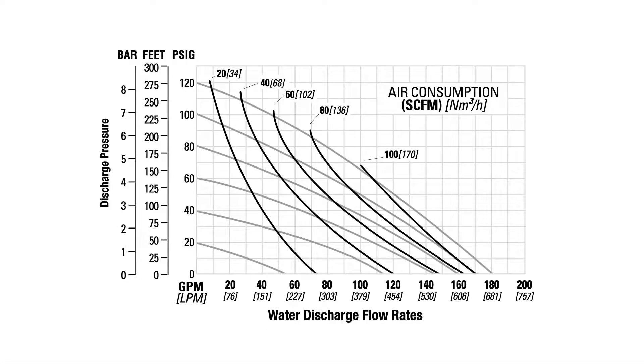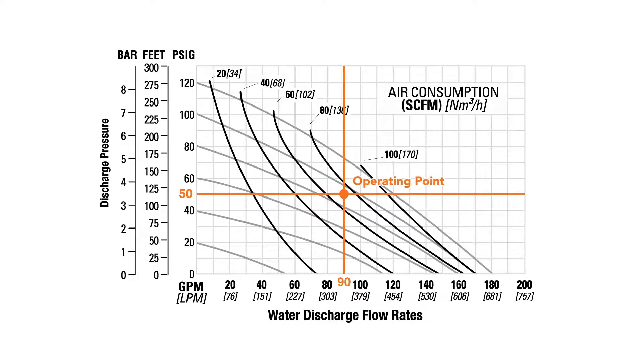The AODD pump performance curve also defines the pump's air consumption, which can be used to help size a compressor for your system and identify opportunities for cost savings. Using the same operating point — pumping 90 gallons per minute at a discharge pressure of 50 PSIG — the performance curve identifies air consumption by following the black vertical curved axis, which lies between 60 and 80 SCFM. You can expect the AODD pump's air consumption to be about 72 SCFM.